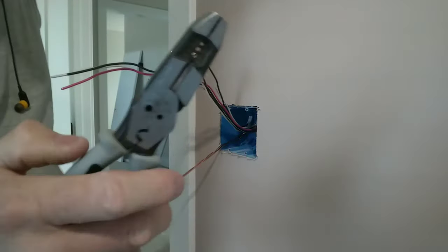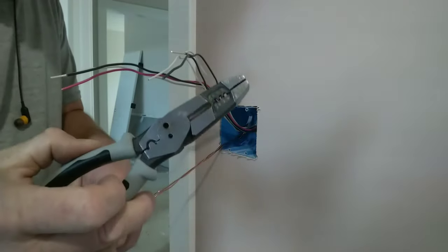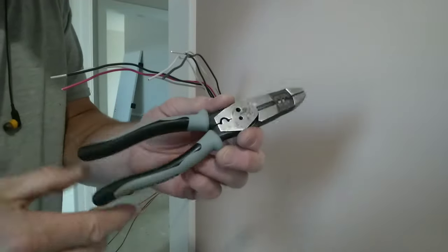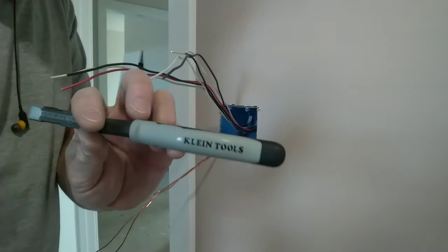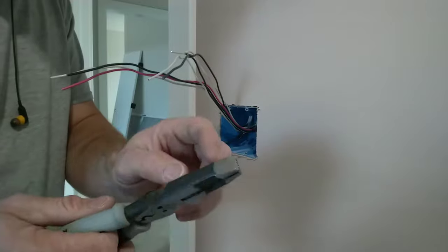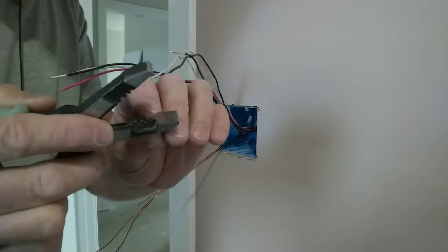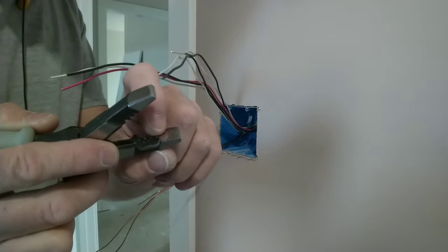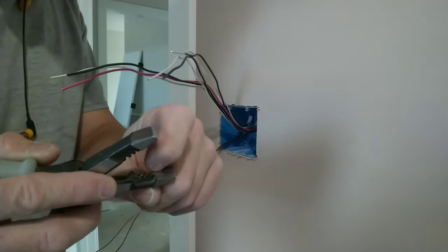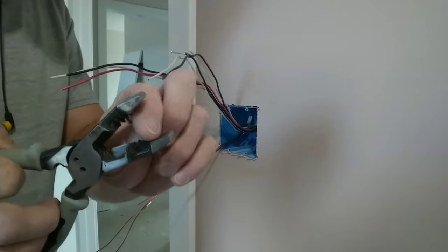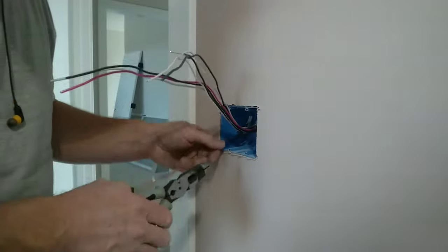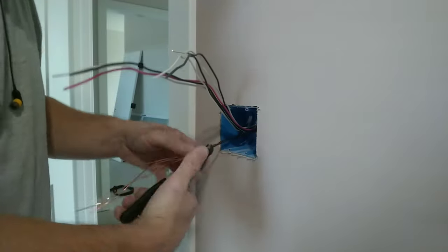Now, in this particular hybrid plier, if you haven't modified this yet, I'm going to do a video in the future on this hybrid lineman's plier with the gray grip, and it is made by Klein. There's one problem with these, and it is inside of the jaw, there's a line that goes across here that on a brand new pair of pliers, I grind that line off. That line, if you don't alter that and take that sharp edge off, you will score these grounds, and as you are bending them in the box, they will break off.